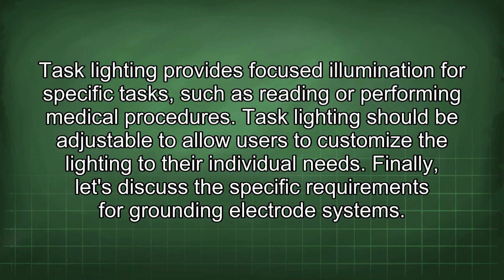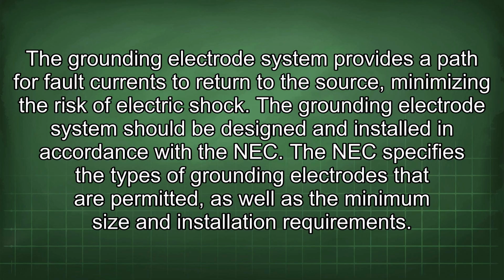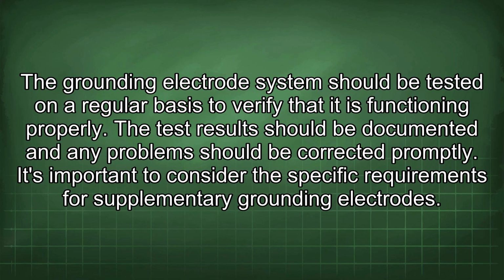Finally, let's discuss the specific requirements for grounding electrode systems. The grounding electrode system provides a path for fault currents to return to the source, minimizing the risk of electric shock. The grounding electrode system should be designed and installed in accordance with the NEC. The NEC specifies the types of grounding electrodes that are permitted, as well as the minimum size and installation requirements. The grounding electrode system should be tested on a regular basis to verify that it is functioning properly. The test results should be documented and any problems should be corrected promptly.